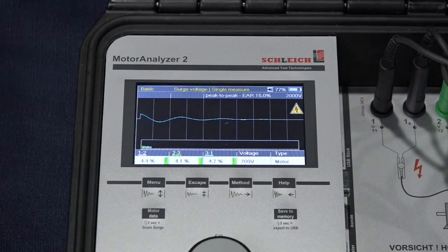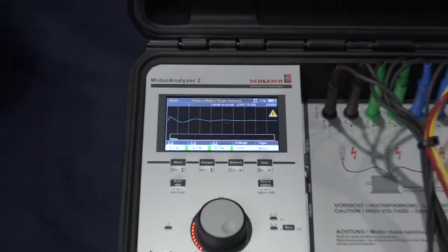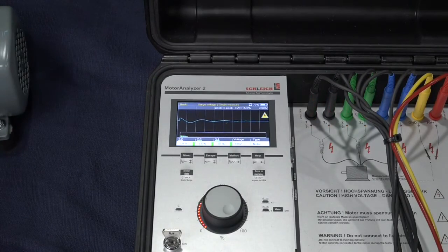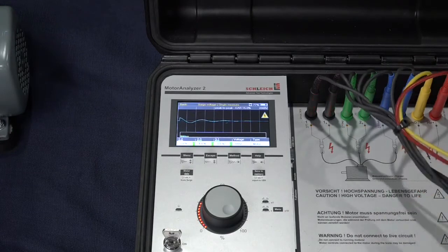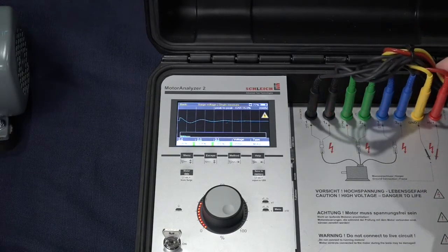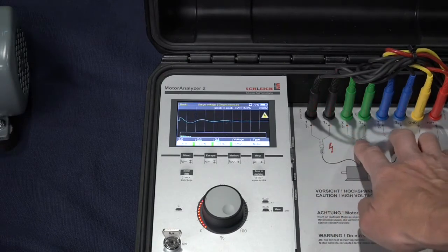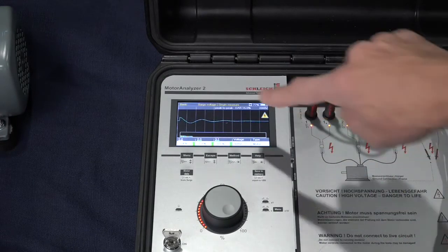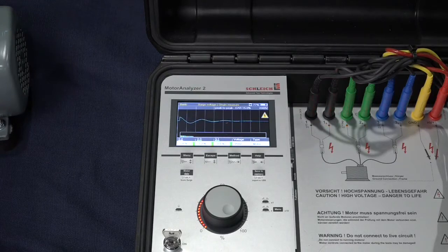Again, I've got to emphasize that this instrument runs differently than almost any other tester you've ever seen. You can see the test leads there are pretty active. Let's make it so you can see it. So you'll see it do a 1 to 2, a 2 to 3, and then a 3 to 1. It takes each one of those waveforms and plots them on the screen, and then calculates a peak-to-peak or pulse-to-pulse error area ratio. If we ever need to stop the test, we press the start-stop button and off it goes.